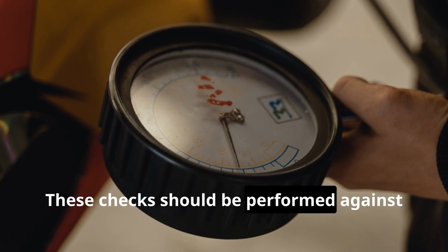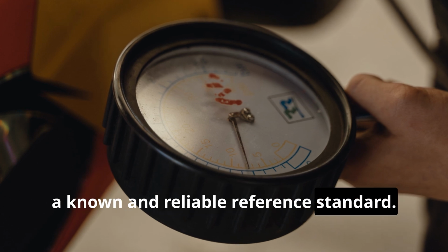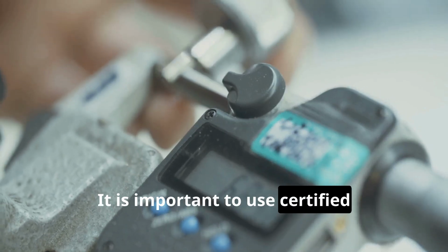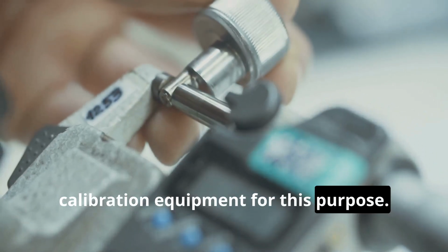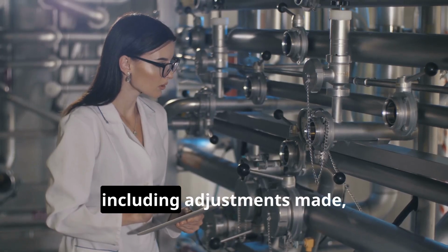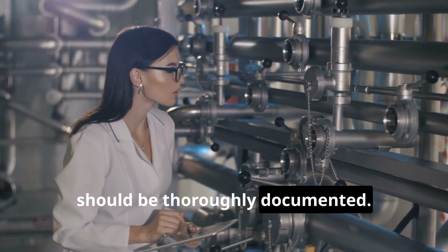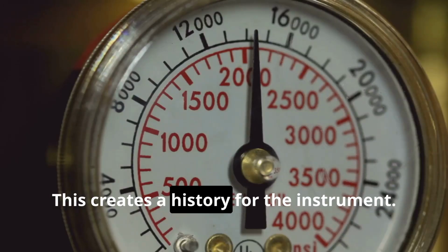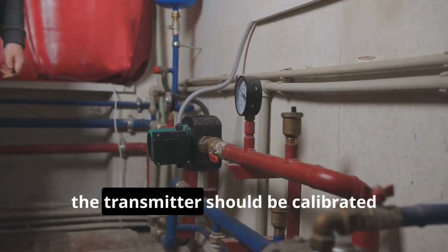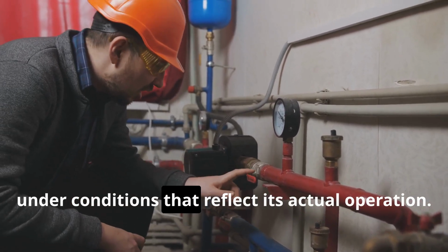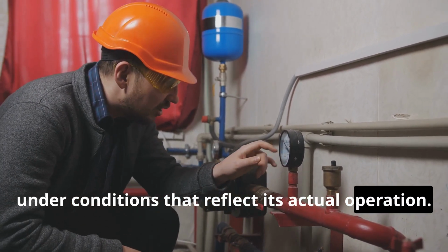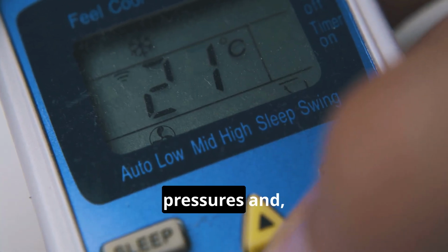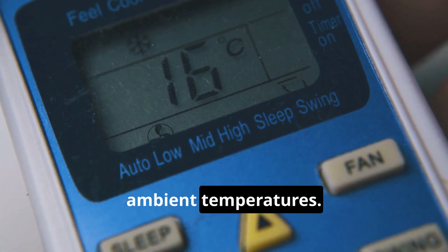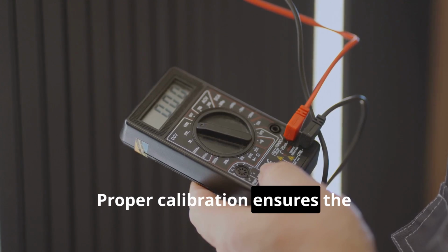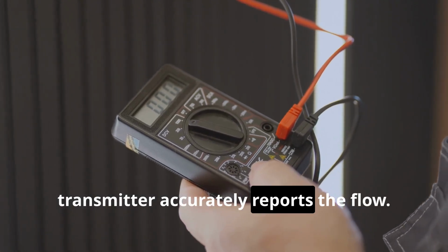These checks should be performed against a known and reliable reference standard. It is important to use certified calibration equipment for this purpose. All calibration activities, including adjustments made, should be thoroughly documented. This creates a history for the instrument. Critically, the transmitter should be calibrated under conditions that reflect its actual operation. This includes the expected range of pressures and, importantly, ambient temperatures. Proper calibration ensures the transmitter accurately reports the flow.